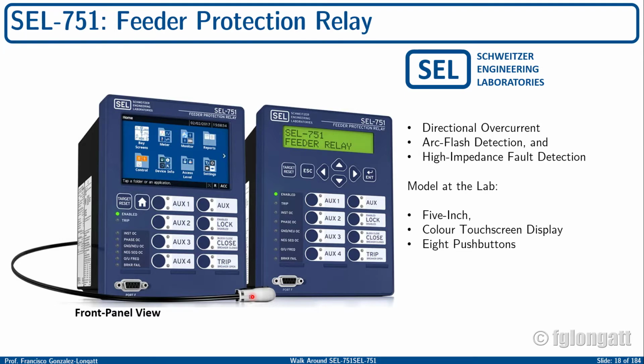And I would like to focus a bit of time here on this sensor, because this 751 is equipped with what we call arc flash detection. The idea is that this is a sensor installed in order to detect arc flash in a very fast fashion, and we are talking about around 2 milliseconds. That means that it's possible to detect when an arc is happening at the equipment, and in this case, the relay offers a combination of light and high speed overcurrent protection in order to solve issues related with arc flash events.